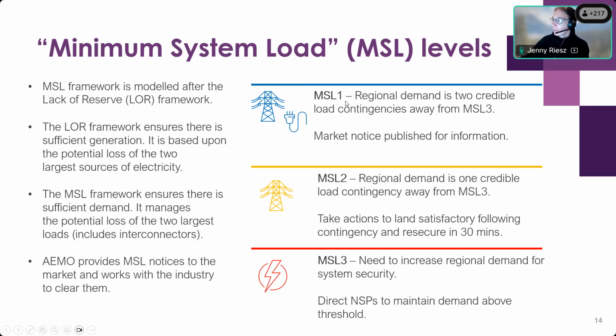MSL1 is the level of demand where we're two credible contingencies away from MSL3. At that level, we would publish a market notice as an information for the industry. MSL2 is the level of regional demand where we're one credible load contingency away from MSL3. And at that point, we start to take actions to make sure that if that contingency happened, we would remain satisfactory, which means that everything is still within limits, and we could re-secure, so get back to a point of being one further contingency away within 30 minutes. And MSL3 is the level where we need to increase demand to maintain system security. So we would see some sort of violation at that level. And at this level, we'll direct our network service providers, or NSPs, to maintain demand above that threshold.